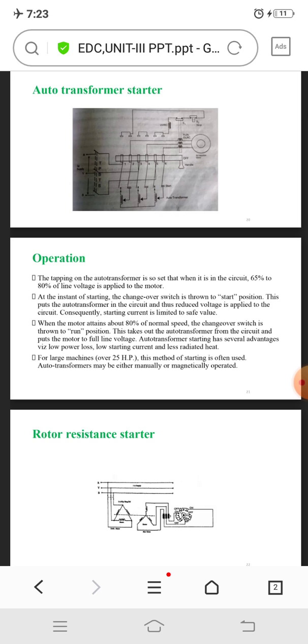Auto transformer starting has several advantages, viz. low power loss, low starting current, and less radiated heat. For large machines over 25 horsepower, this method of starting is often used. The auto transformer may be either manually or magnetically operated.